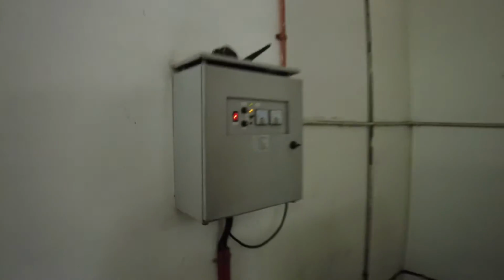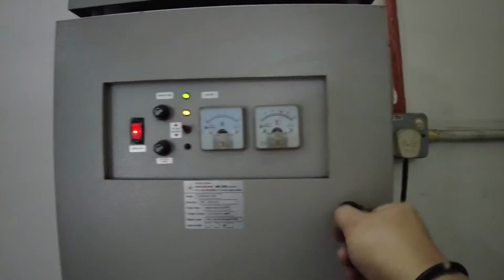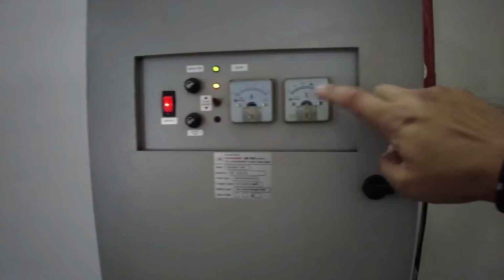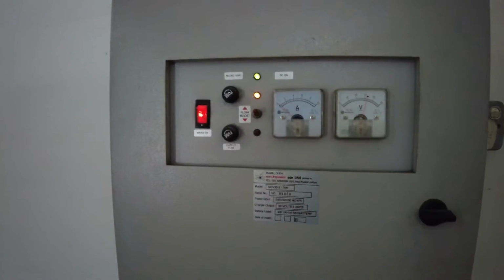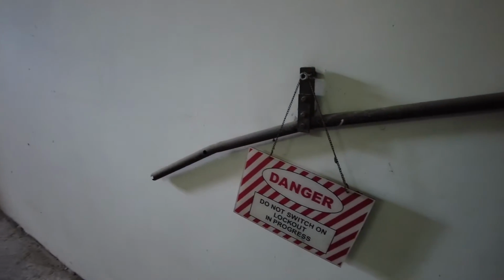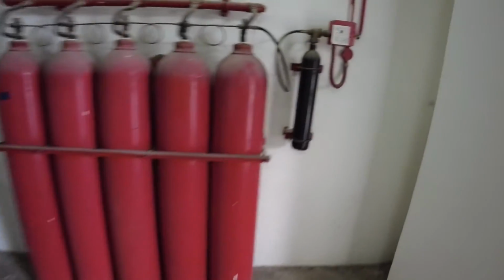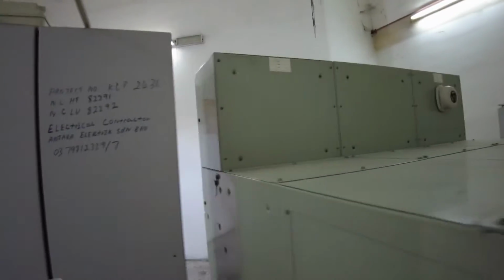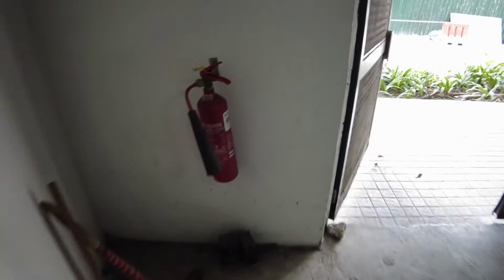Here we have a nickel metal hydride tripping unit battery cell, which we call dry cell. 30 volt DC. Charging amp is okay. Rack in, rack out tools in place. Signage, rubber mat, CO2 extinguishing system in place, nothing unusual. Earth strip copper tape, earthing is okay. Fire extinguisher in place.